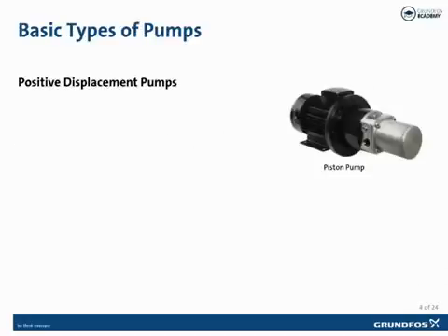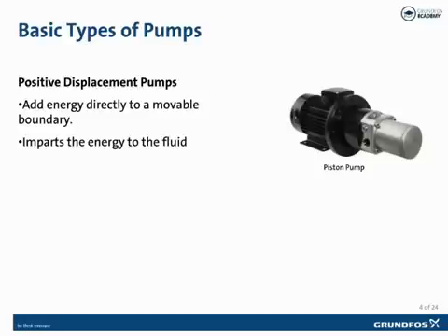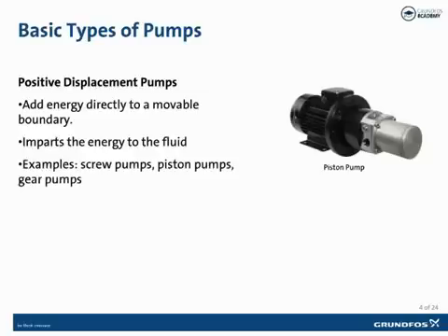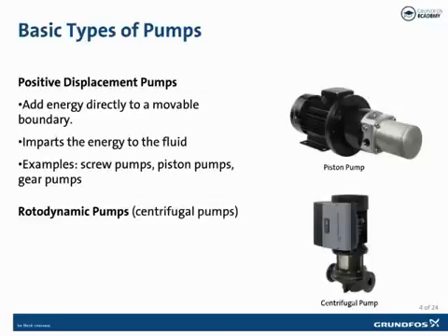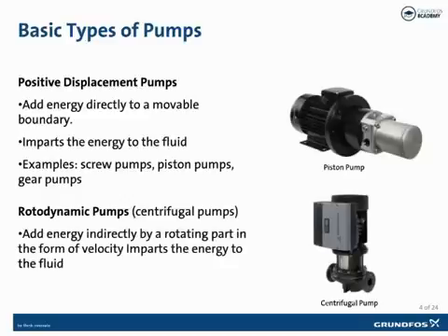There are two basic types of pumps. Positive displacement pumps, also known as PD pumps, add energy directly to a movable boundary to impart energy to the fluid. Examples of PD pumps are screw pumps, piston pumps, or gear pumps. The second type are rotodynamic pumps, commonly known as centrifugal pumps or CPs. They add energy indirectly by a rotating part in the form of velocity, then converting that velocity to pressure. Centrifugal pumps are the workhorse device in HVAC systems, and we'll concentrate on them for this training module.